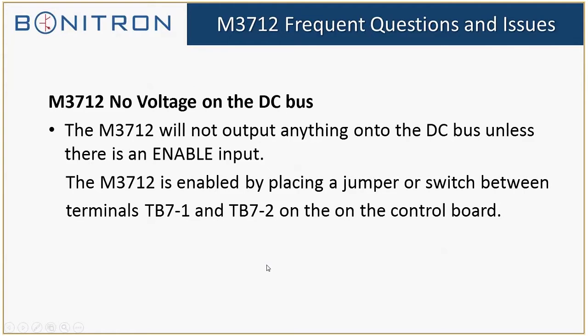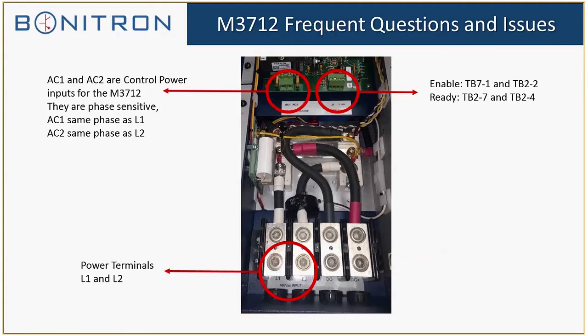So for me, I'm very visual, so I like seeing how the unit actually looks. This is an example of our M3712-H050, our 50 horsepower version of the M3712. The AC terminals are down here, L1 and L2. These should be connected to the power after a line reactor. And then we have our actual control board AC terminals up here. The sticker says AC1 and AC2. If you're looking at what is written on the silk screen on the board, the terminals are marked TB1-1 and TB1-2. Typically, I just tell customers AC1 and AC2 because it's big and they can see it as soon as they open the cover.